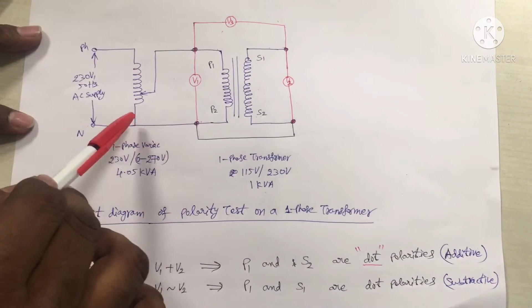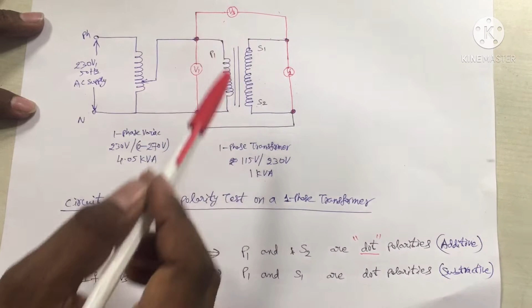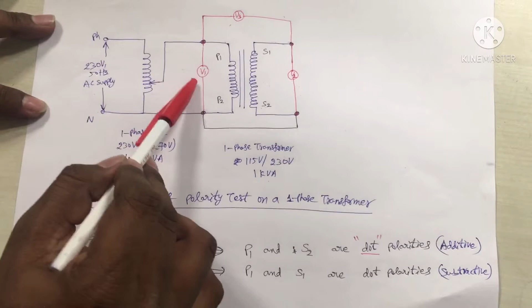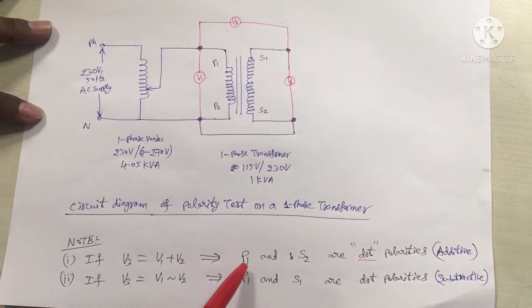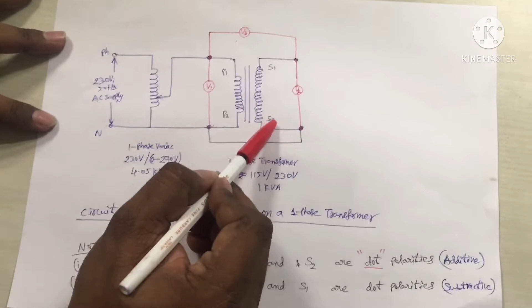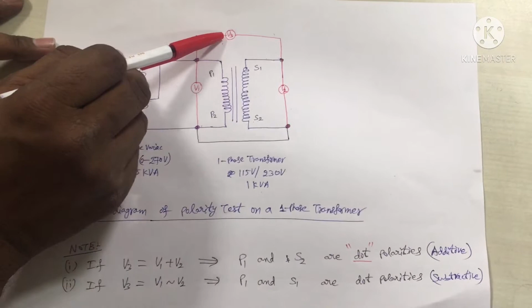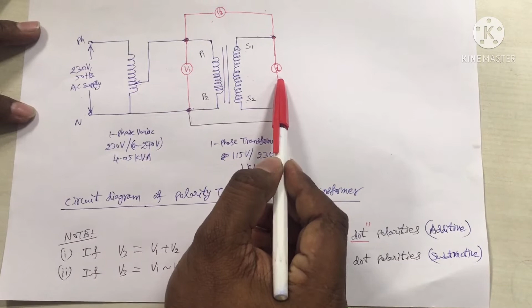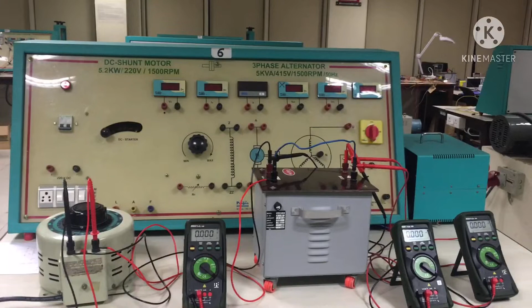If the supply voltage is given to the transformer primary winding through the single phase variac, we can see the V1, V2, V3 values. If the V3 voltmeter gives the sum of the V1 and V2 voltmeter readings, then it indicates that the P1 and S2 terminals will be dotted. If V3 measures the difference of the V1 and V2 voltmeter readings, then P1 and S1 will be the dotted polarity. We have connected this circuit as per the given circuit diagram.